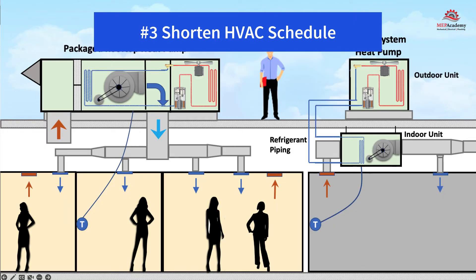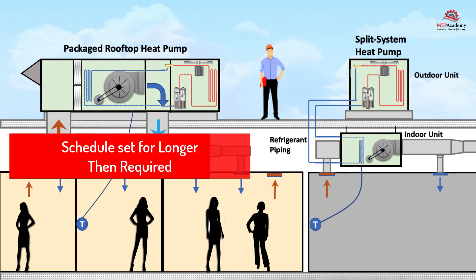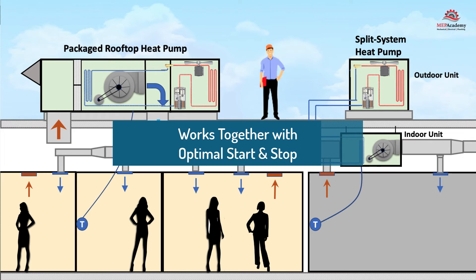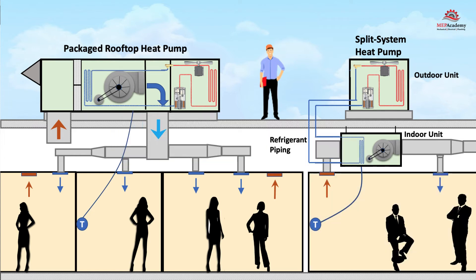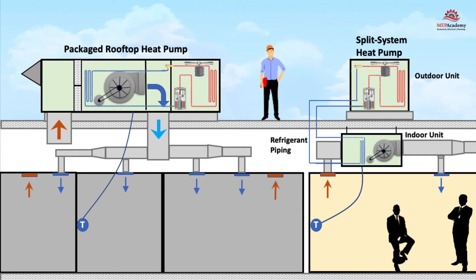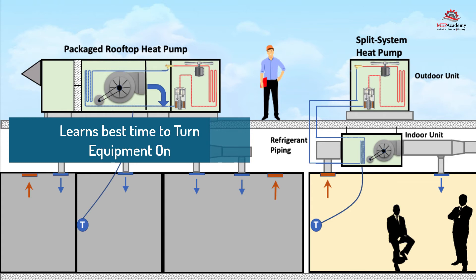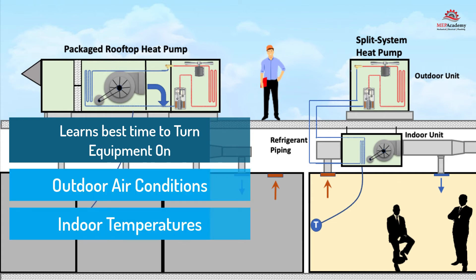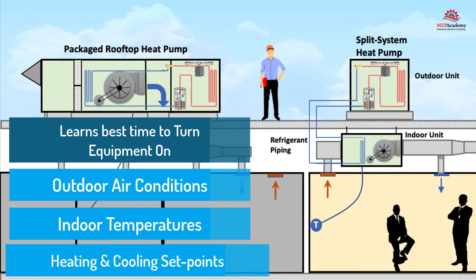Number three: shortened HVAC schedule. HVAC schedules are often set for longer time durations than actual occupants require. Shortening the HVAC schedule works well with an optimal start and stop control strategy. This strategy avoids turning on HVAC equipment before it is needed and quickly turns it off when occupants are not scheduled to be in the building. The building automation system learns with historical trending data when it's the best time to turn equipment on, using outdoor air conditions, indoor temperatures, and setpoints for heating and cooling during occupied mode.